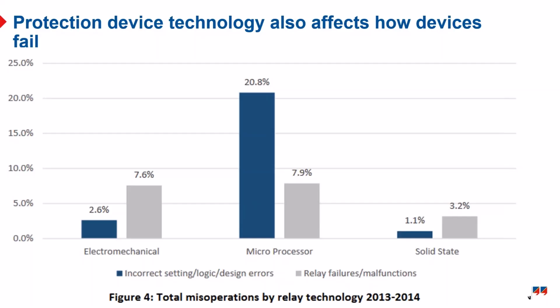On the other side, the actual relay failures and malfunctions, you can see that the rate of failures for electromechanical relays is fairly substantial. And I think the comparison between electromechanical and microprocessor here is important, because this is 2013, 2014, and the bulk electric system, that's the system above 100 kV. There were far more microprocessor relays in service than electromechanical relays. So you can't really compare the relay failures and malfunctions between the two classes directly. Likewise, the solid state relays had such a bad reputation and such poor performance over the years that there aren't very many of them left on the bulk electric system. They're still around here and there, but definitely the minority.